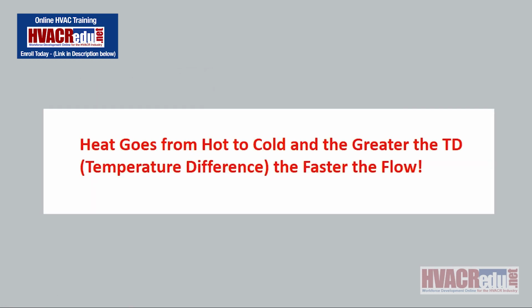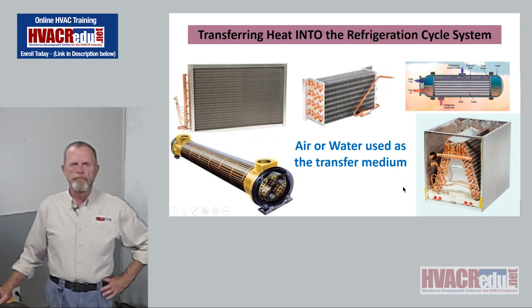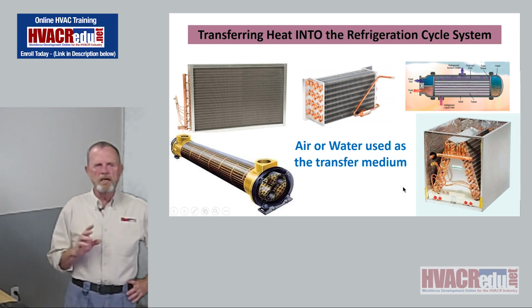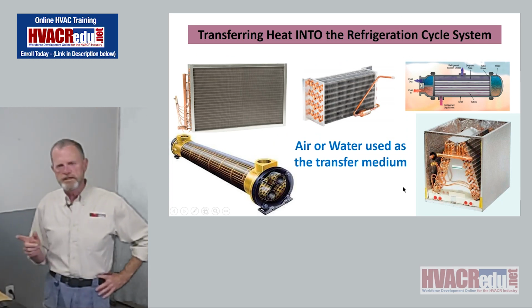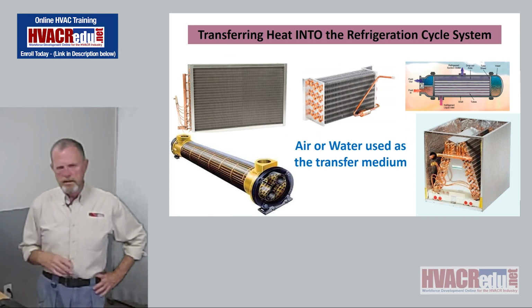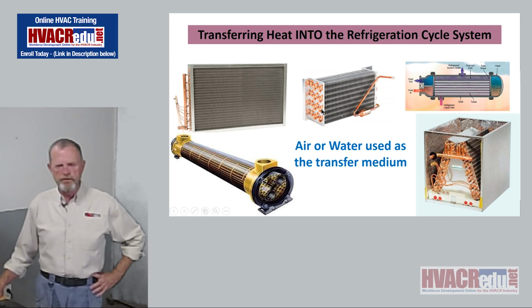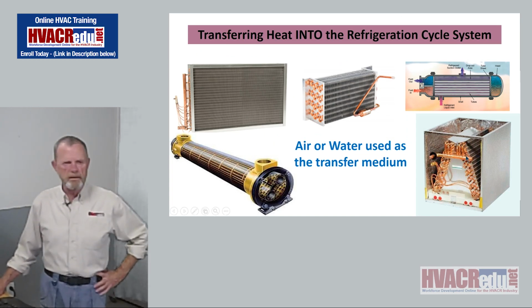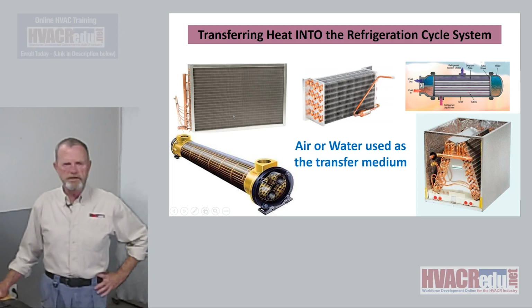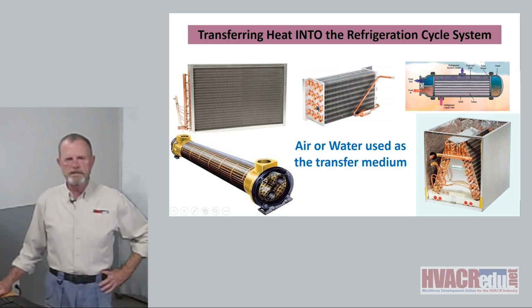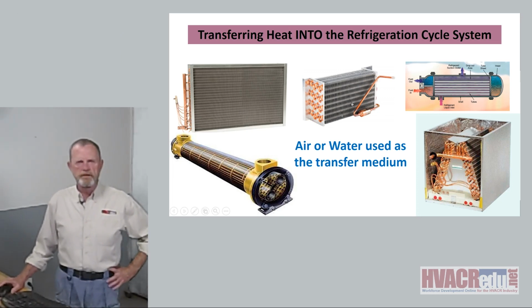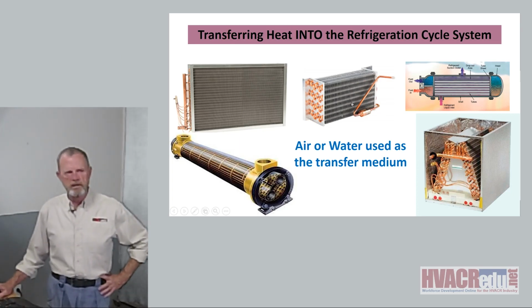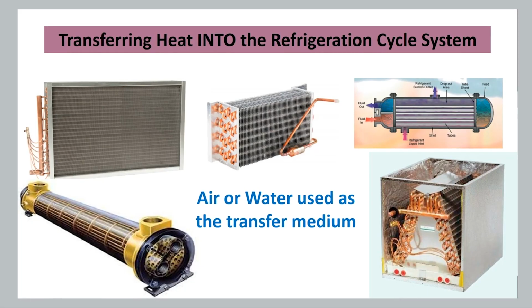Remember, heat goes from hot to cold, and the greater the temperature difference, the faster the flow. So this session is all about transferring heat into the refrigeration cycle. And I've got images up here. I've got 3 air evaporators, or evaporators used in airstreams. Obviously, copper coils, aluminum fins on the coil, and so on. You guys have seen these, you know what they are. All these are fresh coils. There are no metering devices on them at this point.